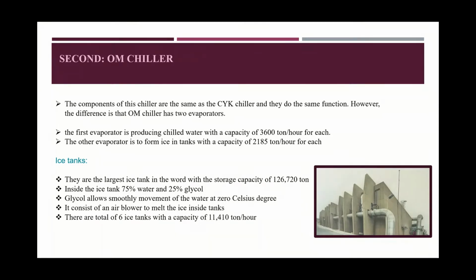When it comes to the ice tank, they are the largest ice tank in the world with the storage capacity of 126,720 tons. Glycol, which is a chemical compound, is added to water that enters those ice tanks through pipe. Thus, it allows smooth movement of the water at 0 Celsius degrees, so the water does not freeze. Inside the ice tank, there is 75% water and 25% glycol. Also, there is an air blower to melt the ice inside the tanks, used during daylight, while the ice is formed at night time to save energy.